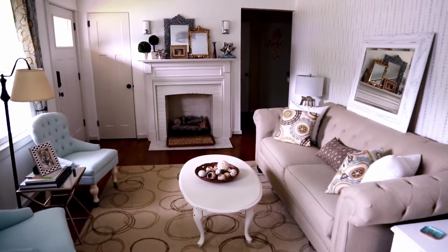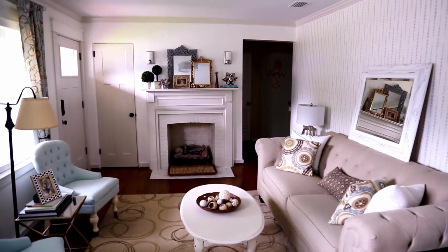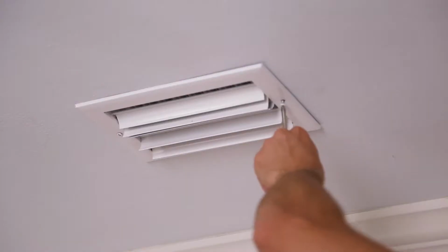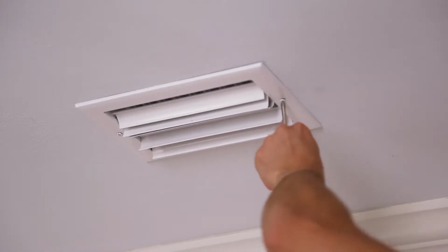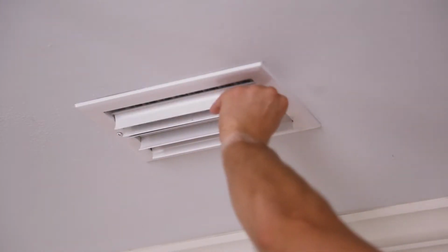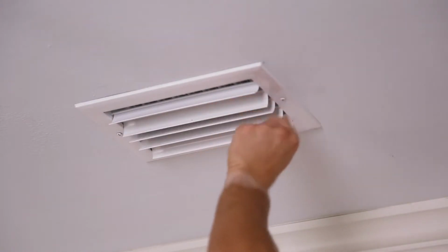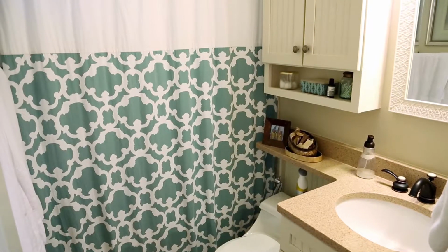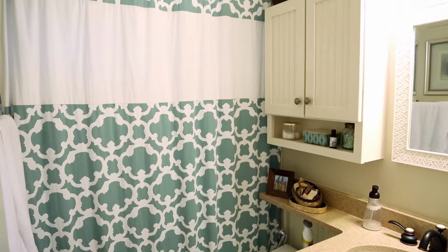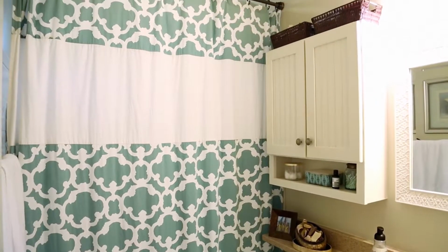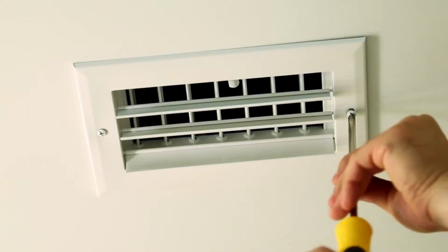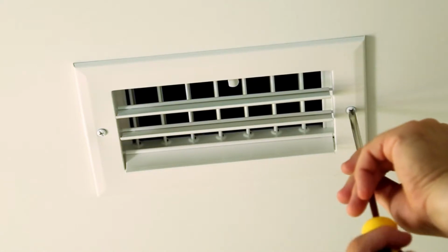Now it's time to install the exhaust or distribution registers. As mentioned previously, you will likely want to install the stale air exhaust registers in a bathroom, kitchen, or living room. Position the registers as far as possible from a stairway, and so that the air circulates in the living space. Registers can be installed in the ceiling or on an interior wall 6 to 12 inches below the ceiling.